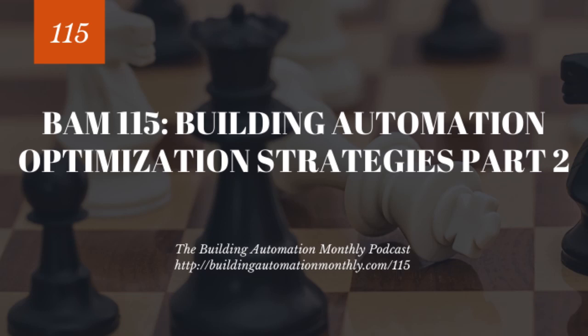So by being aware of enthalpy, you are deciding what is going to take more energy: cooling down some maybe warmer but much drier return air, or introducing all this humid air into my system and having to flush that out? So that is another way of economizer optimization.